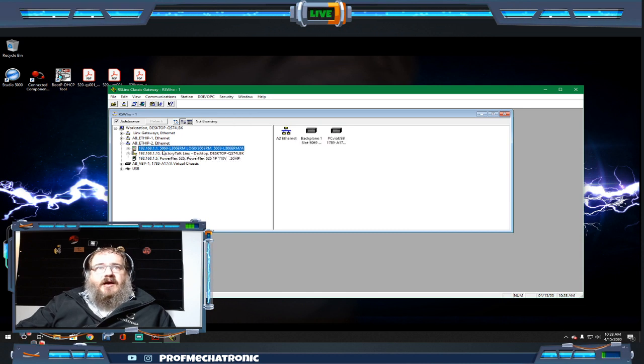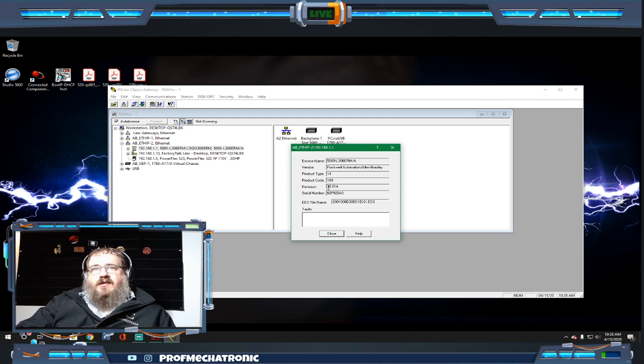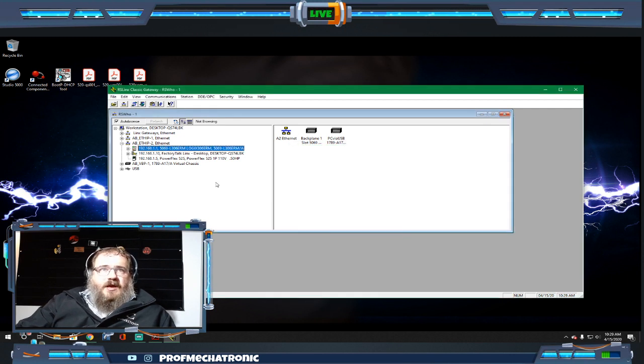And then we have our actual PLC here as well. We can do the same thing, go to device properties. We can see that the revision of our PLC is version 30. We can see the serial numbers, a whole bunch of information about that actual PLC in here as well. Now the revision codes of our drive and PLC don't have to match. There's no requirement for that. They do firmware upgrades at different states and at different times, so we don't have to worry about those being the same or having any correlation between them at all.